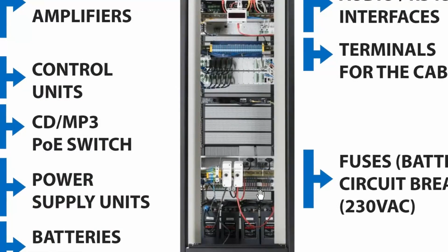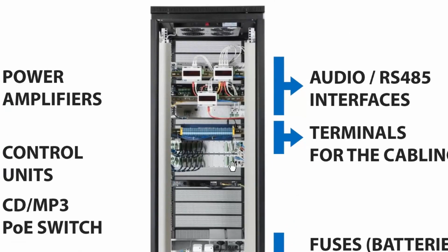So if you can see over here, we've got our power supply system, and the power is distributed inside the rack to different components. In case of mains power failure, the batteries are responsible for delivering power to the rest of the system. Usually the batteries must be designed to deliver 24-hour standby, and then either 30 minutes or 60 minutes of full power after the standby.